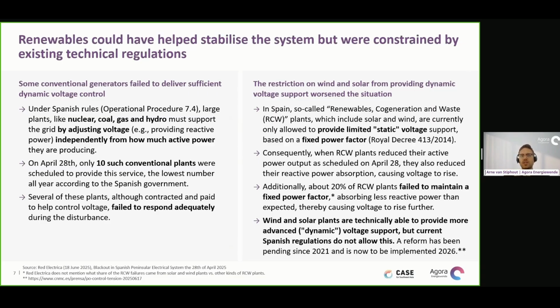And then actually there were also some issues with some of the plants to deliver this fixed power factor, which made this problem worse. There was even less reactive power absorption for the plants operating at low active power levels. So again, higher voltages. And all of this together is actually the main thing that we want to underline here: this fixed power factor, this static voltage support, there is no reason to limit these plants to this.